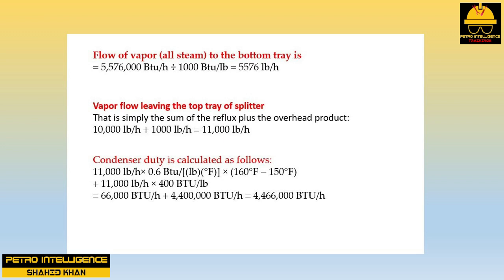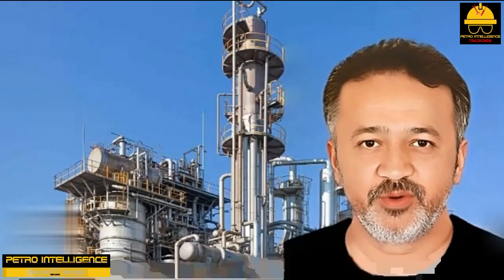The vapor flow leaving the top tray is simply the sum of the reflux plus the overhead product: 10,000 lb/hr + 1,000 lb/hr = 11,000 lb/hr. Condenser duty is calculated as follows: 11,000 lb/hr × 0.6 BTU/lb·°F × (160 − 150)°F + 11,000 lb/hr × 400 BTU/lb = 66,000 BTU/hr + 4,400,000 BTU/hr = 4,466,000 BTU/hr (approximately).